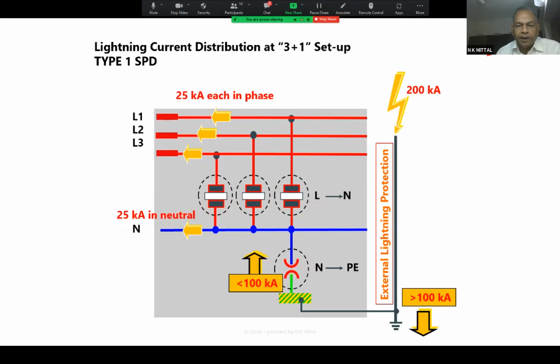Understood. Point is clear. Now, when we are placing an order to some vendor, and in the order we just write 25K into 4 pole, or we write 100K, it is one and the same thing, I assume. No, sir. So it is understood that neutral to earth is 100K in all these cases. No, sir. In fact, please mention 3+1 circuit, line to neutral 25 kiloampere, 10/350, which I told you very importantly, and neutral to earth 100 kiloampere. All these things have to be specified.